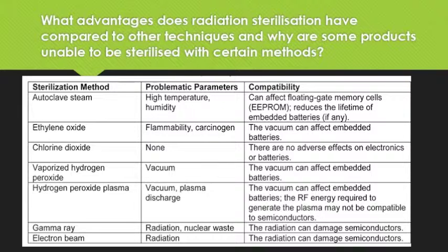Radiation sterilization is ideal for medical equipment, as it would not require a quarantine period and would not require the facility to purchase any more equipment to make up for the equipment being quarantined.